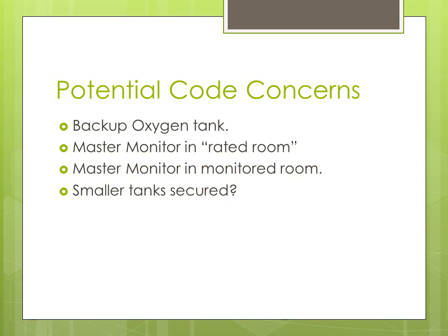We didn't see a backup oxygen tank. There should have been a little tank there. The master monitor, I had put a question: I wonder if it's in a rated room, and we'll talk about that in a minute. And is the master monitor in a monitored room? And then also, are the smaller tanks secured? So let's go back and look at this again, and look at those things.